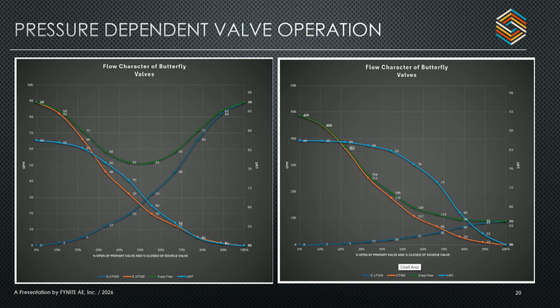The first graph that's closest to us on this side shows that if you have both valves with a 0.01 pressure drop, almost nothing on them, and they're equal, even as the valve modulates open, you could have up to a 40, I think that's 40, yes, up to a 40 gallon per minute decrease as this valve is blending, trying to maintain your leaving water temperature. Our chillers are 54 GPM, so a 40 GPM decrease is enough to cause them to trip out.